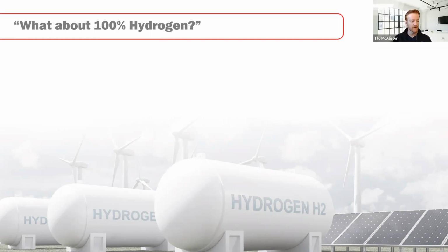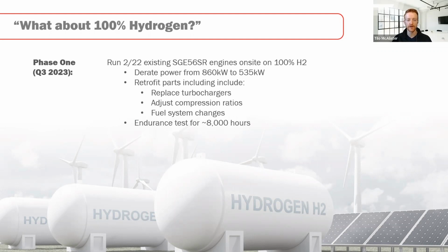So our plan right now, expected to be complete by fall 2023, is to convert 2 of the 22 SR engines on site as a pilot project to run on 100% hydrogen. We're going to derate these—their nominal output on natural gas is about 860 kilowatts of electrical power, and we'll derate them to be safe down to 535 kilowatts. We'll do more extensive retrofits, including swapping out the turbochargers, pistons, and changes to the fuel system and compression ratios. We'll endurance test these units for up to 8,000 hours over the next year to see how they do. We expect they'll do pretty good, but we'll learn a lot from the data.